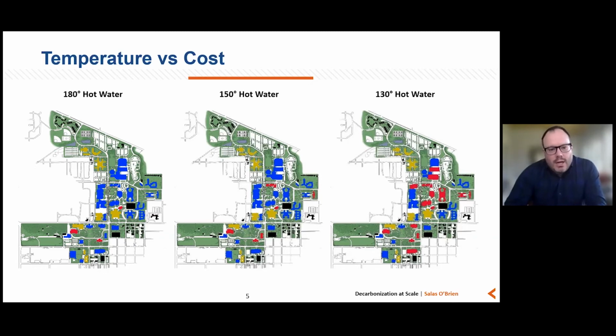What we often do for district settings is do setback tests in the period of the year that we're about to enter here. The November through early February timeframe will offer you a very cold window of opportunity where you can start to set back the supply hot water temperature in the buildings. And instead of doing expensive modeling or expensive testing or metering of various spaces, you really rely on human beings to be your metering device and issue cold calls to your facilities or to the program manager for this kind of effort. At Ball State, we started at 180 degrees and moved all the way down to 130 degree hot water temperature and found which buildings were really going to create issues from a comfort perspective. That allowed us to pick the hot water supply temperature that would be most cost effective to do the building conversion work.